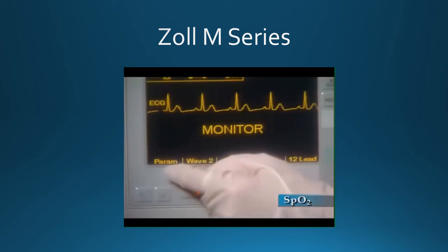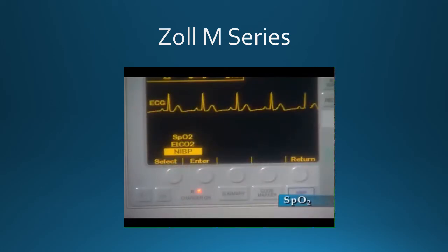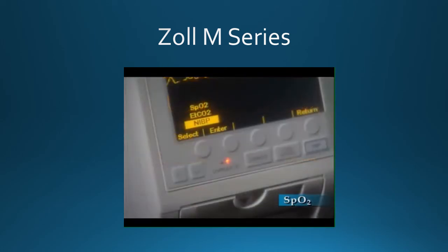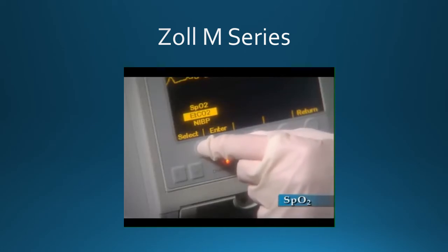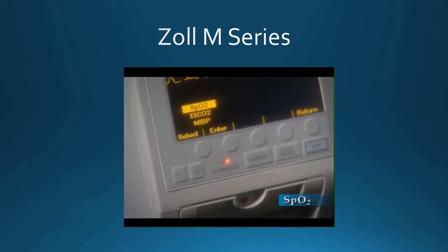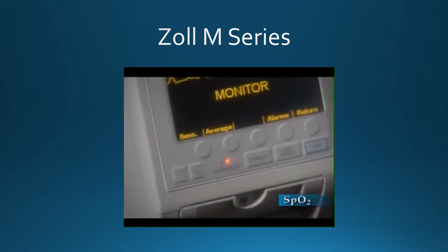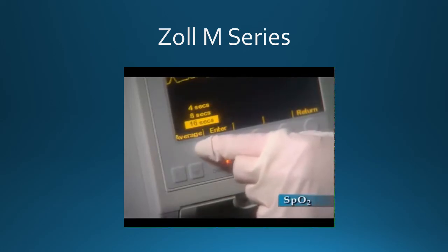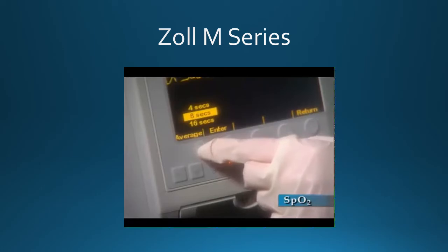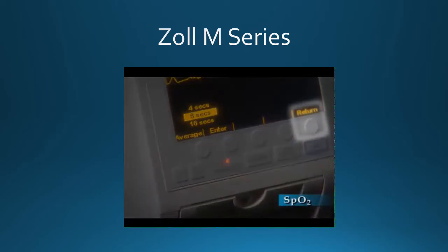When the parameter soft key is pressed, the Select, Enter, and Return soft keys will be displayed. Pressing the Select soft key allows you to scroll through different physiologic parameters if available. Selecting the SPO2 soft key causes the following soft keys to appear: Sensitivity, Average, Alarms, and Return. The Sensitivity soft key allows the user to select either normal or high sensitivity for SPO2 monitoring. The normal setting is recommended for most patients. The Average soft key provides 3 different time periods over which SPO2 values are averaged: 16 seconds, 4 seconds, 8 seconds, which is the default setting. The Return soft key returns the operator to the previous screen.